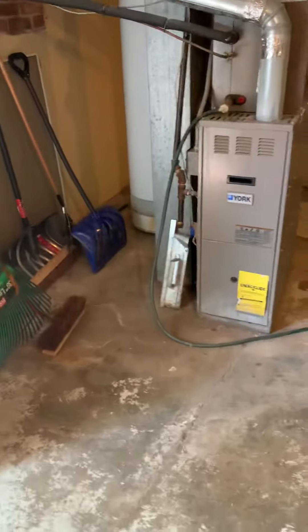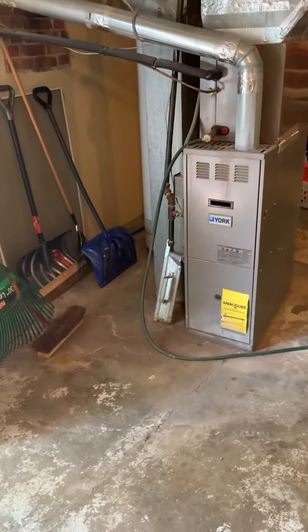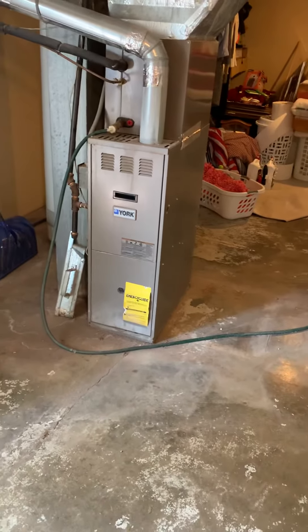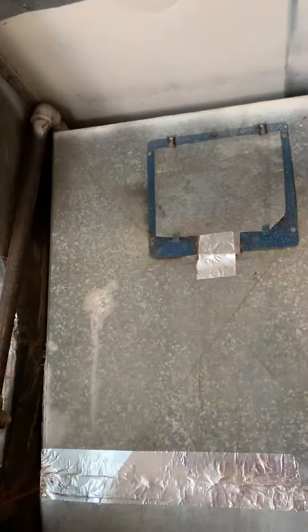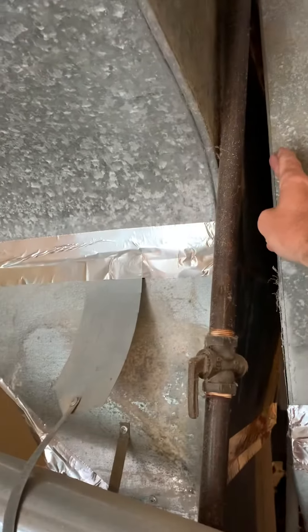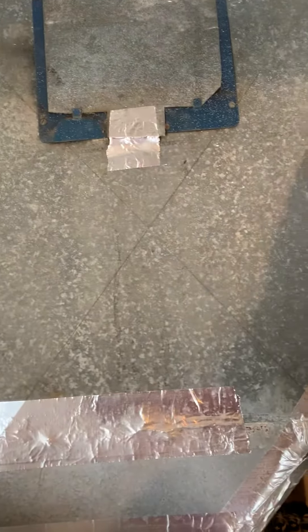Taking a look at a rental property — we've got quite a few things wrong with the outdoor unit and some things wrong with the indoor unit and ductwork. What we're looking at is a new furnace, new coil, and getting this entire piece out. I think it'll actually be easier to go 10 by 21 by 23 with the end cap, and we may want to add a little flex connector to make up that dimension, since we have a gas pipe unit.